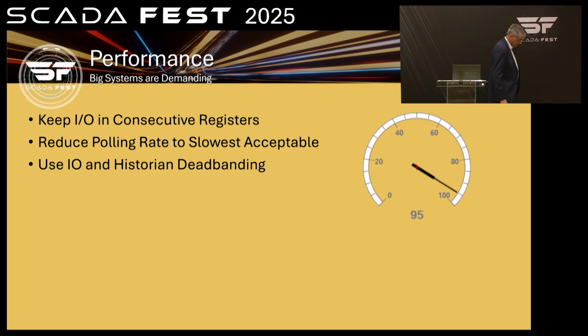Dead banding is really important too, because every time a value comes in, it checks it against the last value and sees, has it changed by this dead band or not? And you use that because on analog values, particularly, there's always some sort of instrument noise that comes in. If you have your dead band set to 0, every little change, which is totally insignificant, gets updated in the system, gets communicated across to all the other VT-SCADA servers. And then the historian dead banding is another step on top of that. It will get logged to the hard disk drive, and you will end up eating up all your disk space.